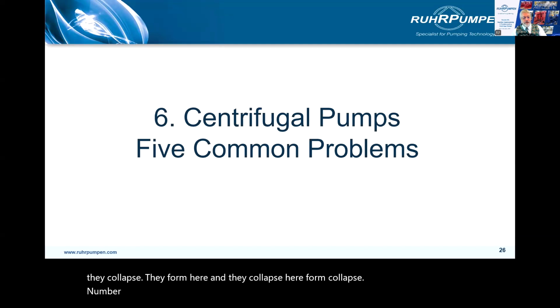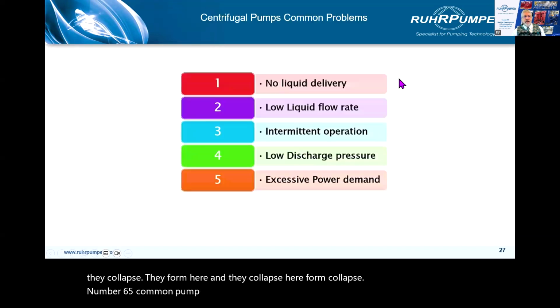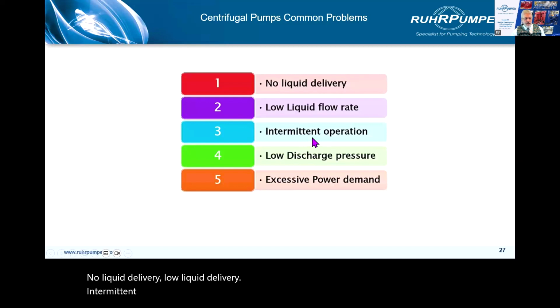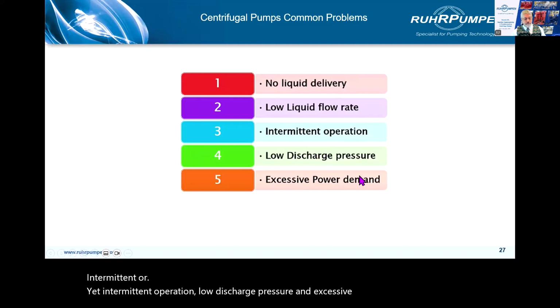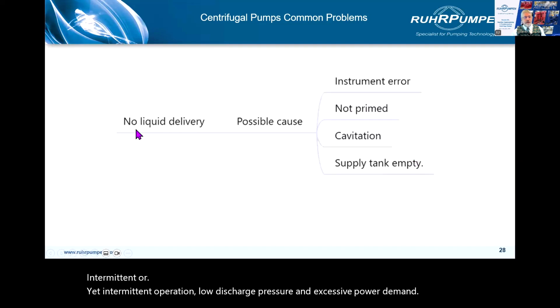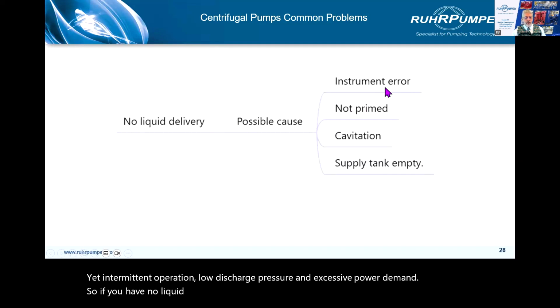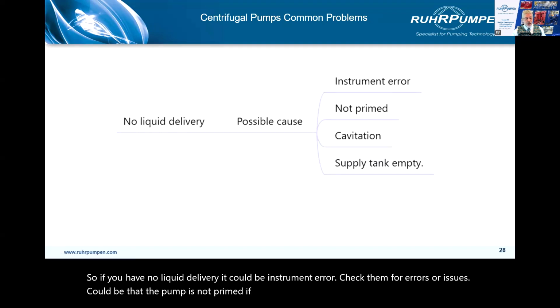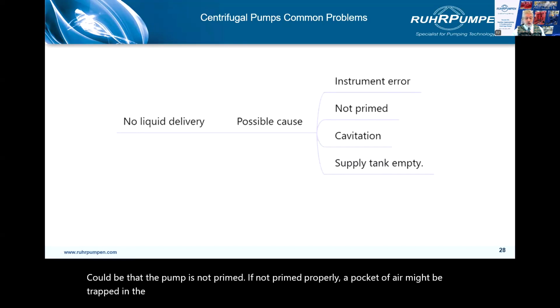Number 6, 5 common pump problems. No liquid delivery, low liquid delivery, intermittent operation, low discharge pressure, and excessive power demand. So if you have no liquid delivery, it could be instrument error. Check them for errors or issues. Could be that the pump is not primed. If not primed properly, a pocket of air might be trapped in the pump, which will not allow centrifugal action to take place.